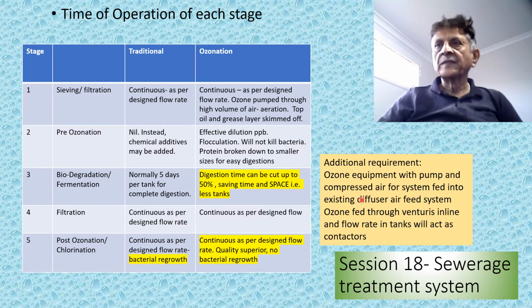In pre-ozonation, the ozone and air mixture is fed through the diffusers or sieve plates located at the bottom, at the floor of the tank. When the resultant treated water is sterilized, ozone is fed online, to the extent of approximately 0.1, 0.5 to 1 ppm. This guarantees that the water is totally sterilized and clear.